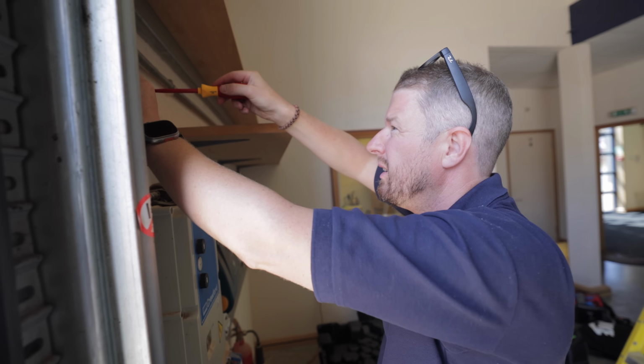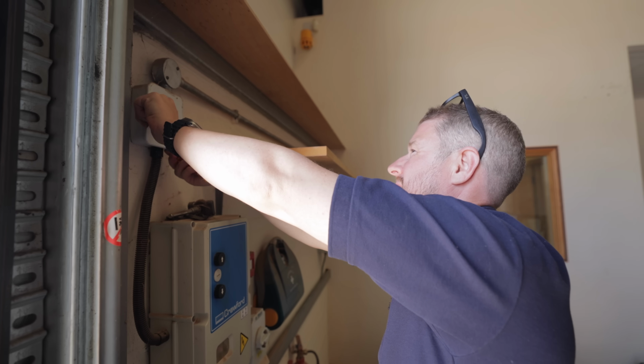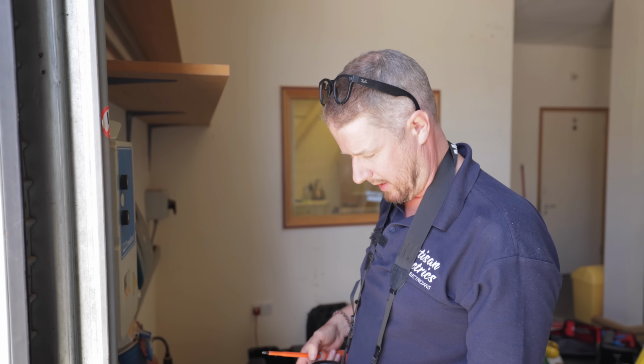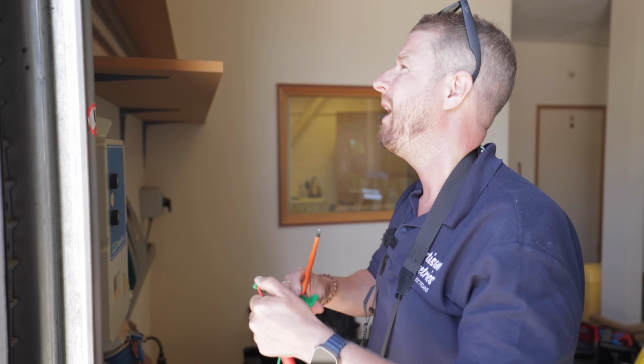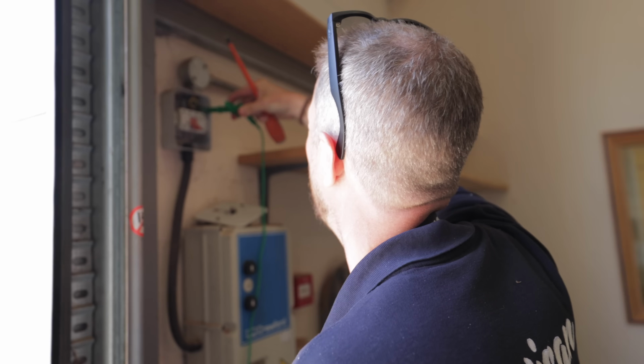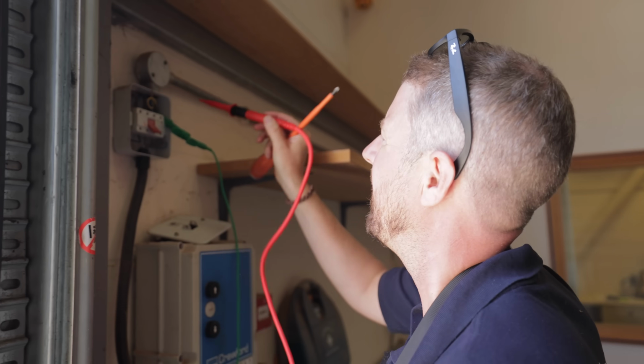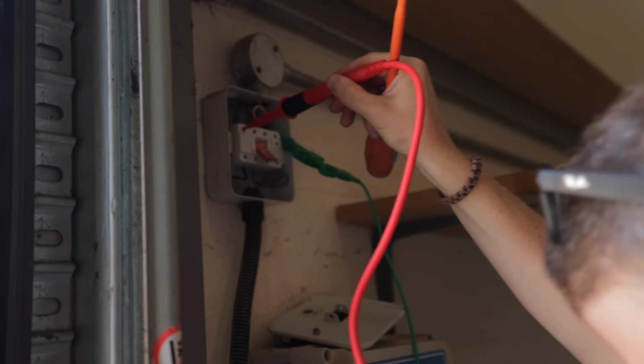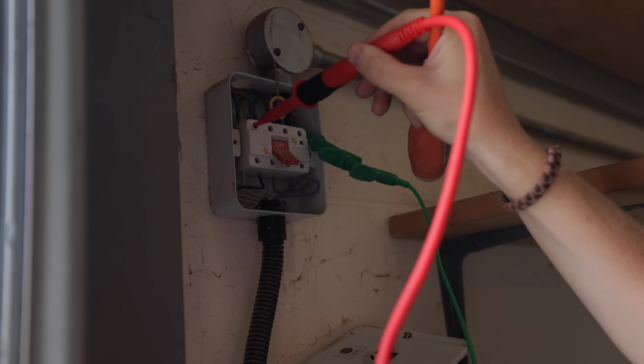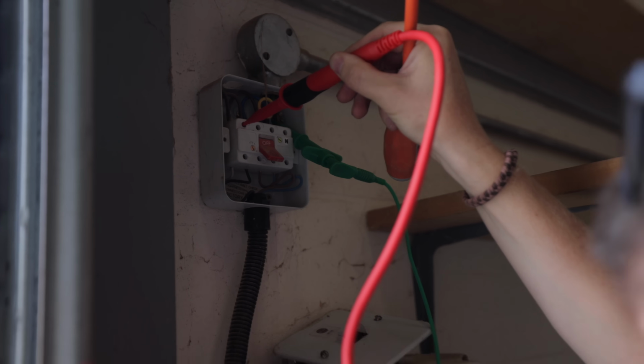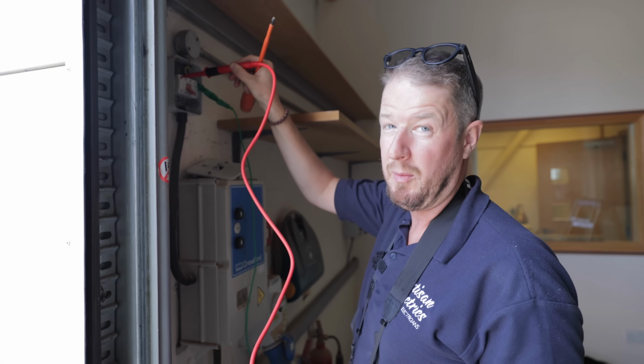Now, when you're testing CPC continuity, it's really important that you null the leads. So I've nulled the leads now, we've got 0 ohms. And then what we're going to do is test from our earth bar here to phase 1. And we've got a reading of 0.07 ohms, which is a nice low reading. Exactly what we're looking for.